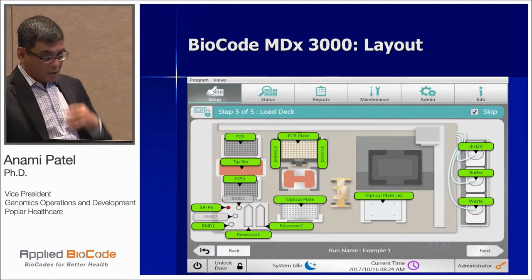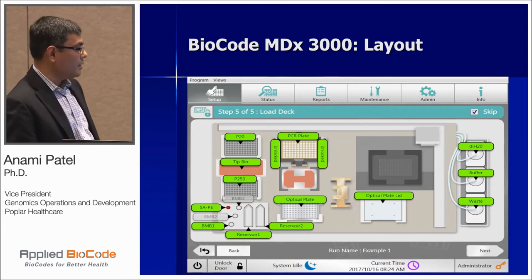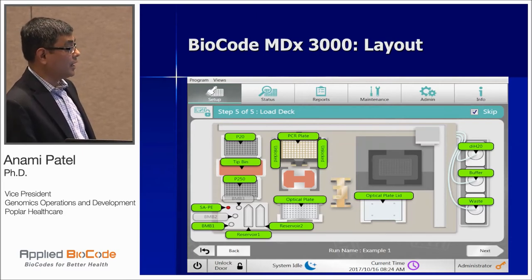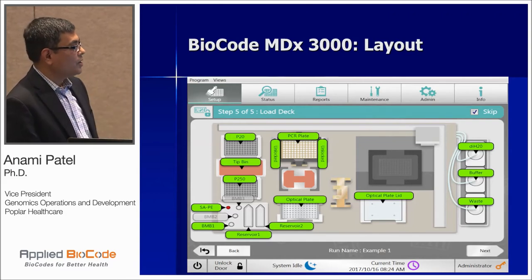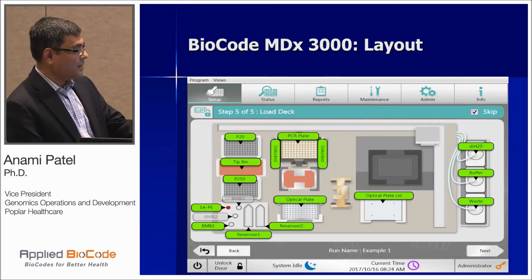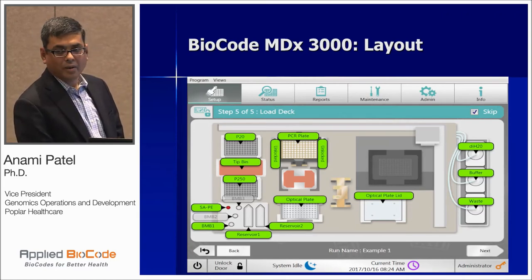Inside the system, once you load your plate and consumables with nucleic acids, it's a single-direction workflow. Essentially, this is a liquid handling transfer. You load your reservoir, BMB mix, SA-PE reagents, and tips, and it takes about three hours to get the final results.